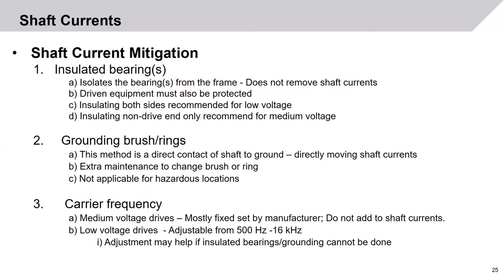The third method, which is really a last resort, is carrier frequency adjustment. This is mainly for low voltage drives. For medium voltage drives, the carrier frequency does not typically add to shaft currents, is set by the manufacturer, and cannot be changed. Low voltage drives can be adjusted from 500 hertz to 16 kilohertz. Again, this is a last resort, and carrier frequency should not be changed unless insulated bearings and/or shaft grounding cannot be done.